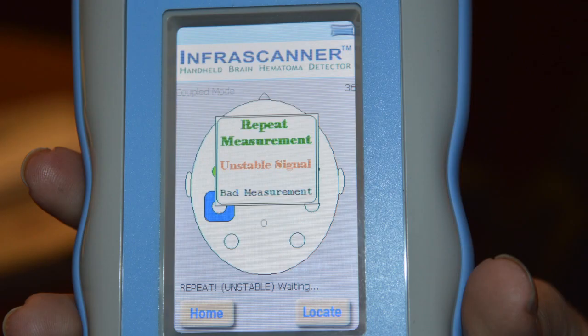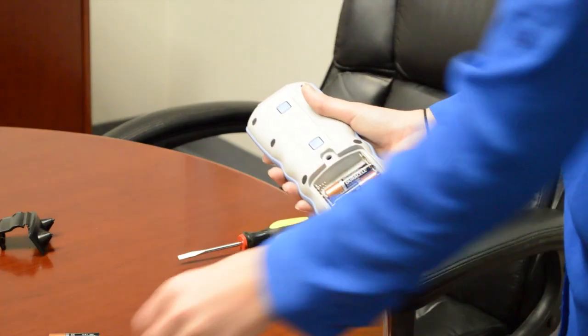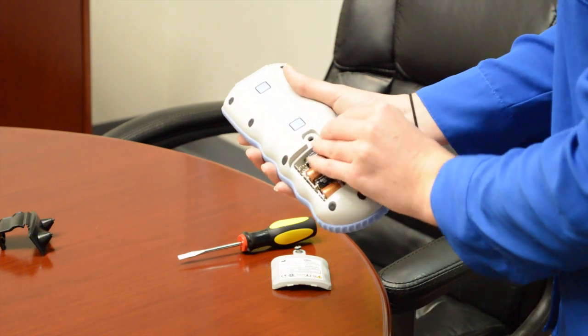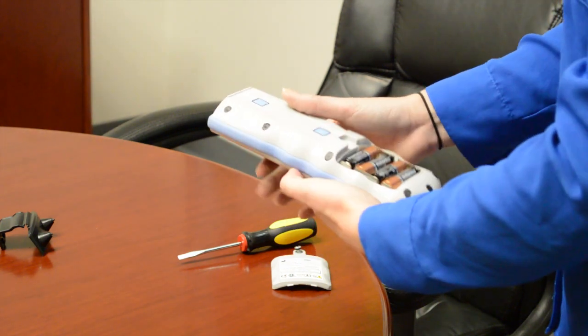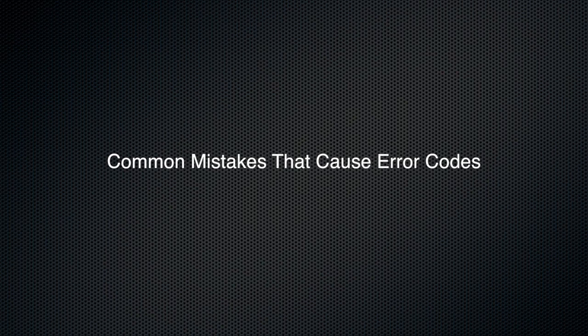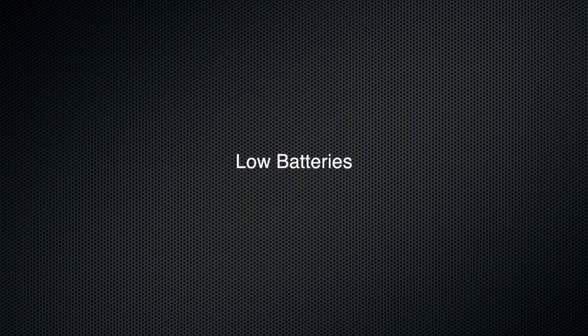Unstable signal. Variations were detected indicating an unsteady reading. Be cautious to use equal pressure so that both prongs are placed on the head and hold your hand steady. Low battery. Time to replace the AA batteries or recharge the battery pack. Some of the most common mistakes that can cause an error code are low batteries, non-uniform pressure, non-symmetrical location for readings, hair under the fiber optic tips, too much overhead light, or hair gel and hair weaves.